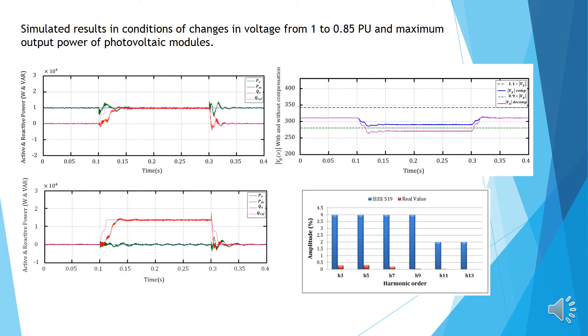In conditional voltage drop from 1 to 0.85 per unit and maximum output power of the photovoltaic module, inverter has produced 10 kW reactive power. In the down figure, active power is zero and the inverter is offered all its capacity to supply the reactive power while it compensates the voltage of the grid as shown in top figure on the right. In this case, the THD is 1.6%.